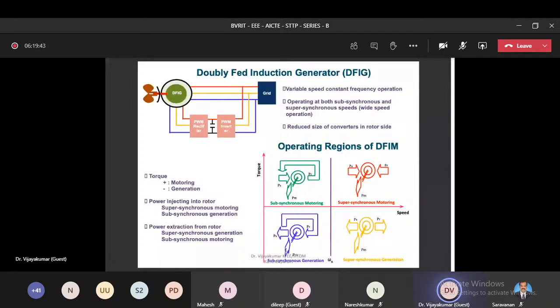But look at the power flow in the rotor. During subsynchronous generation, you are injecting power into the rotor—taking power from the grid and injecting it into the rotor coils. So the power flow is in this direction.